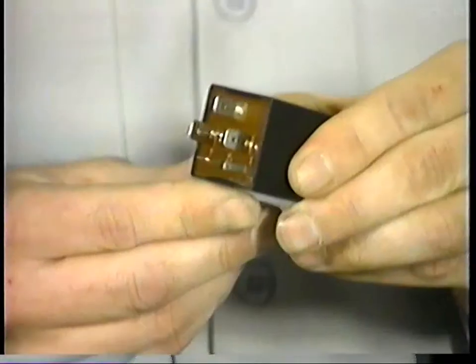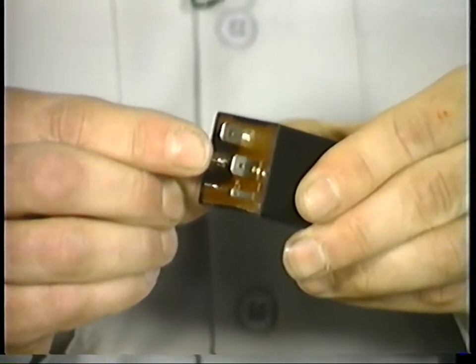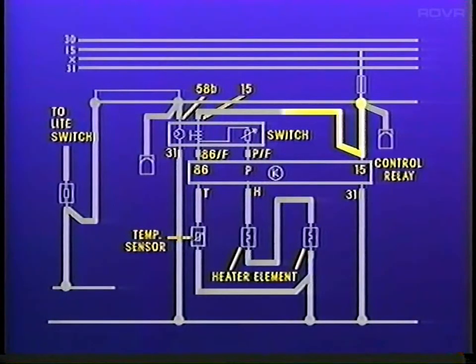The control relay receives its power at terminal 86. This activates the relay. The regulated voltage from the heater switch goes to terminal P. The control relay switches power on and off to the heat elements via terminal H, depending on the resistance of the temperature sensor in the heat element and the temperature that you've selected with the switch.